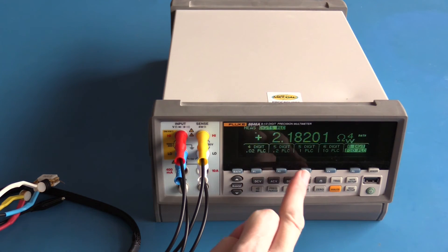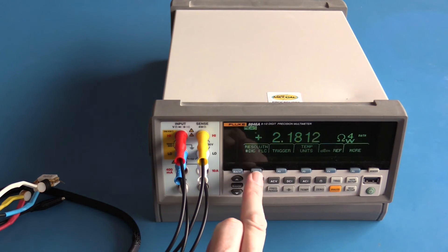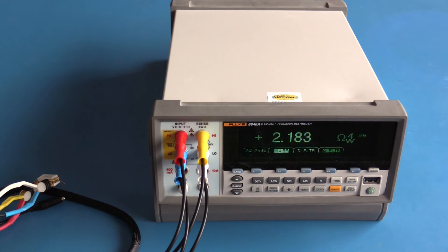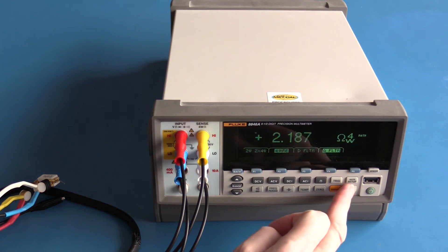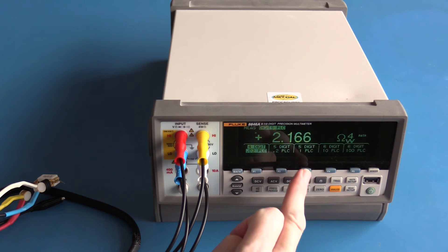I'm going to change that to my preferred five and a half digit resolution, and now I'm going to change to the lowest resolution. At six and a half digit resolution we had a very nice stable reading. At four and a half digits of resolution I think the display is being updated too quickly. This again shows the good compromise between a very quick update at low resolution and a very slow update at high resolution.